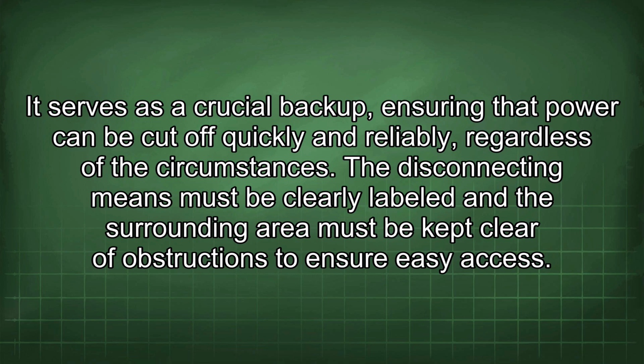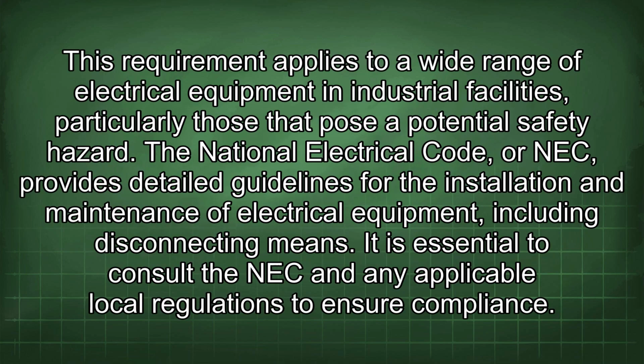The disconnecting means must be clearly labeled and the surrounding area must be kept clear of obstructions to ensure easy access. This requirement applies to a wide range of electrical equipment in industrial facilities, particularly those that pose a potential safety hazard. The National Electrical Code, or NEC, provides detailed guidelines for the installation and maintenance of electrical equipment, including disconnecting means. It is essential to consult the NEC and any applicable local regulations to ensure compliance.